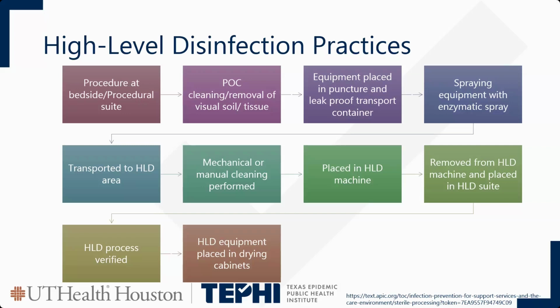That will be doing the leak test, verifying chemicals, talking with staff, asking them how they are cleaning the device as they do it. And then you will see them place that piece of equipment in the reprocessor or the high-level disinfection machine. And at that time, you are checking chemicals. While you're waiting, you're verifying the process. You're looking at logs. There should be traceability and trackability: the serial number along with the cycle time, the QC, and the technician that performed it should all be tracked in your process for accountability.